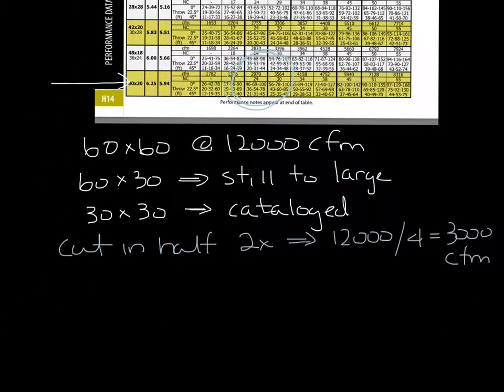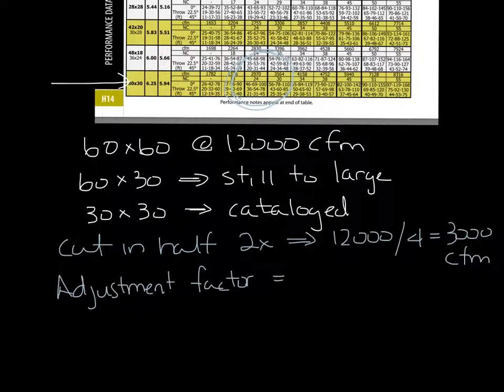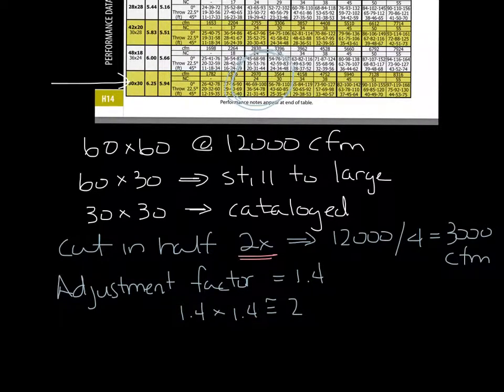Now you use an adjustment factor of 1.4 to determine the throw. Since you cut the grill in half twice, you need to multiply 1.4 times 1.4, which equals 1.96 — we're going to call it 2. So the throw of the 60 by 60 grill will be 2 times the throw of the 30 by 30 grill.